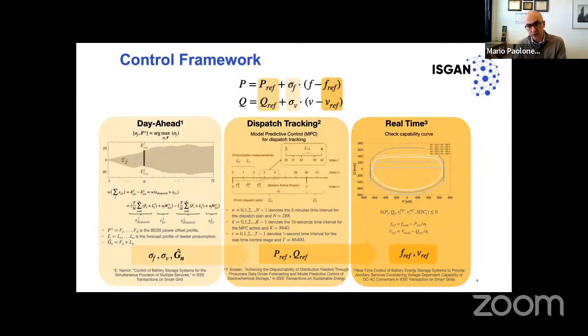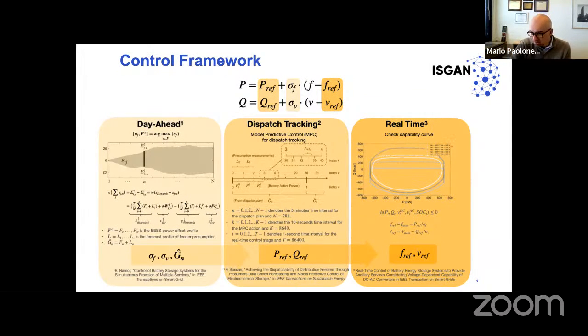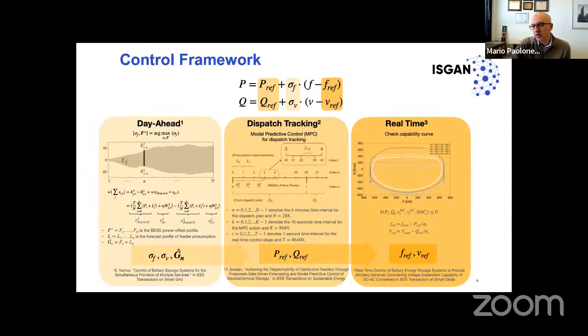Then you have a third layer, the hard real-time layer. What is this layer? Essentially it's a sort of certificate of compliance for delivering the services. You see this graph on the slide, which represents the capability curves of your converters on the PQ plane. These curves are multiple because they depend on the AC and DC voltages on the converter sides. So what you want to do is guarantee that any set point issued by the dispatch tracking, the intraday problem, is compatible with these capability curves. We have developed a framework capable of ensuring this compatibility is satisfied.